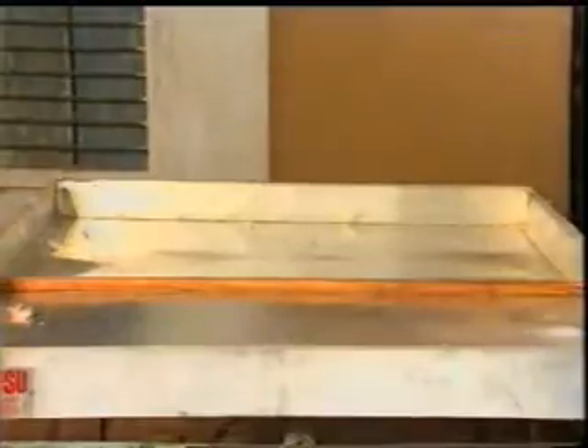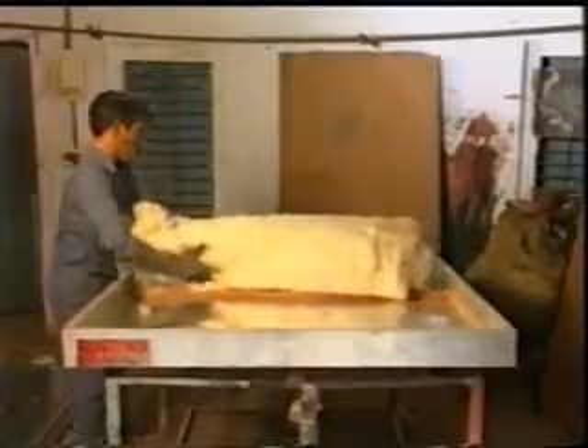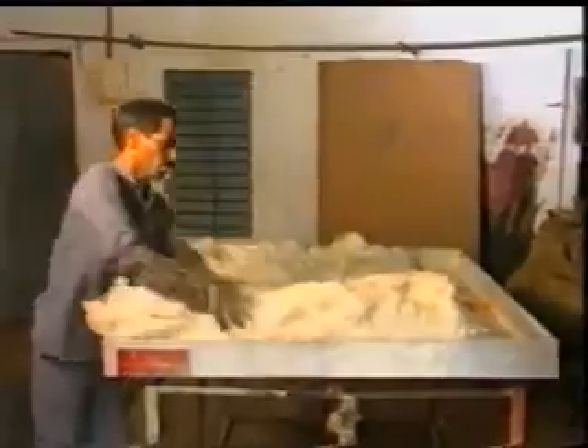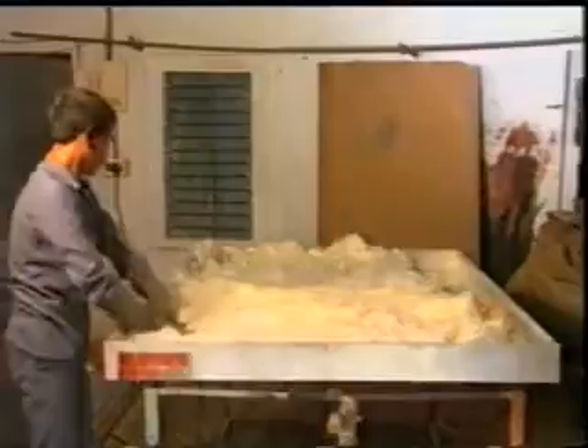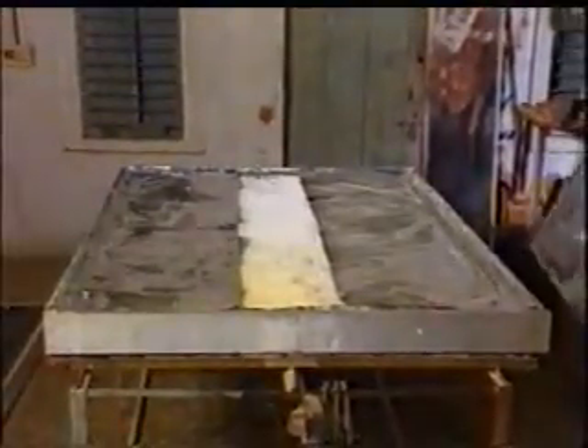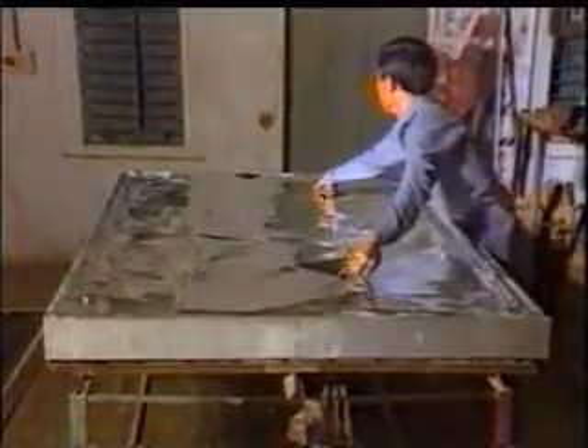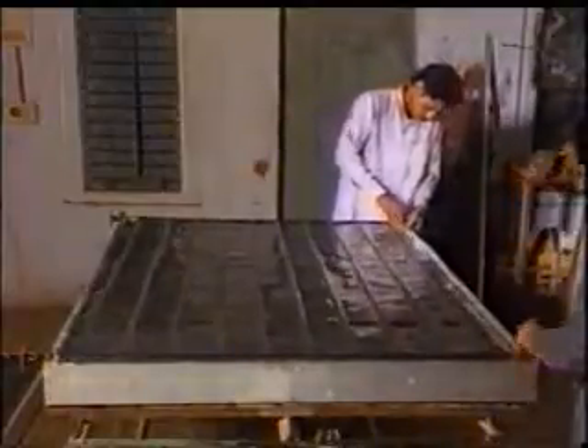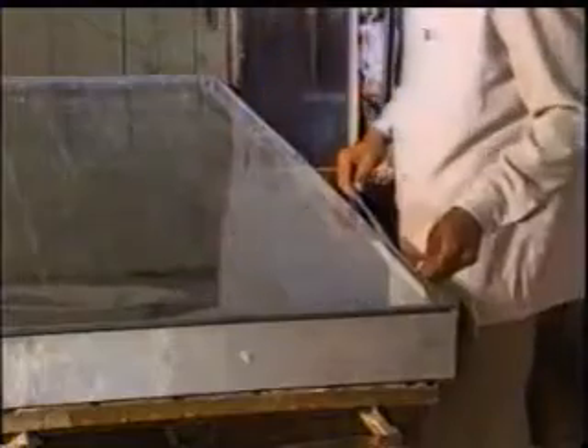The collector casing is an enclosed metallic box in which the insulating material like glass wool is spread throughout the box, to minimize the heat losses from the collector system. The glass wool is covered with thin aluminium foil. After covering the glass foil with aluminium foil, the absorber sheet is fixed upon it. It is covered with toughened glass so as to protect the absorber plate from atmosphere, external foreign bodies, and to transmit solar radiation on to the absorber plate. After that, the frame is fixed.